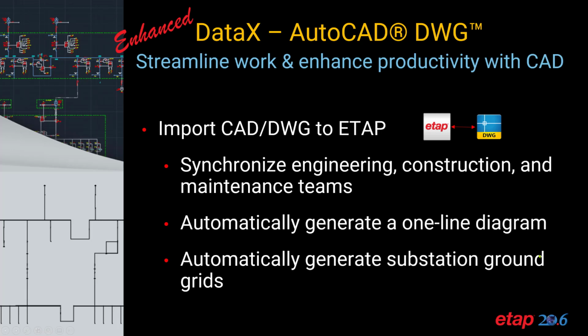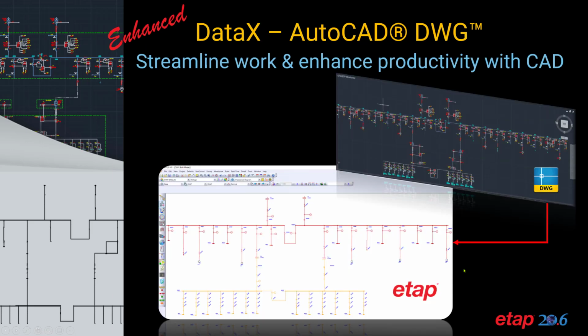The other capability in ETAP that we have enhanced in 20.6 is DataX. It allows data exchange between ETAP and AutoCAD DWG files. By exchanging data between AutoCAD drawings and ETAP, you can streamline work and enhance productivity by essentially reusing the data and not having to manually type the same information all over again. You can synchronize engineering, construction, and maintenance teams, automatically generate a single line diagram in ETAP, and also generate substation ground grids automatically as well.